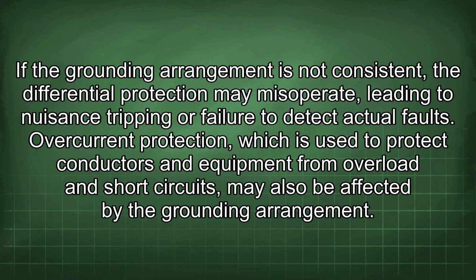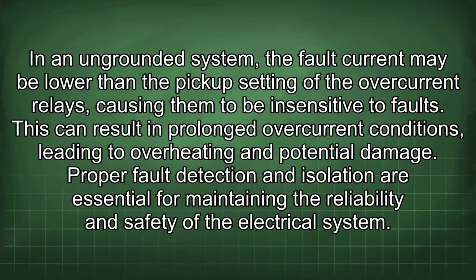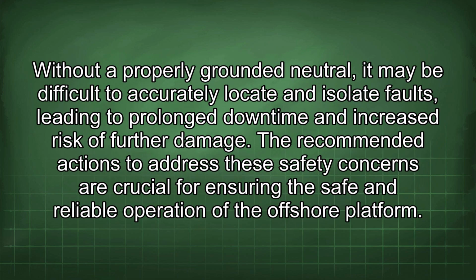Overcurrent protection, which is used to protect conductors and equipment from overload and short circuits, may also be affected by the grounding arrangement. In an ungrounded system, the fault current may be lower than the pickup setting of the overcurrent relays, causing them to be insensitive to faults. This can result in prolonged overcurrent conditions, leading to overheating and potential damage. Proper fault detection and isolation are essential for maintaining the reliability and safety of the electrical system. Without a properly grounded neutral, it may be difficult to accurately locate and isolate faults, leading to prolonged downtime and increased risk of further damage.